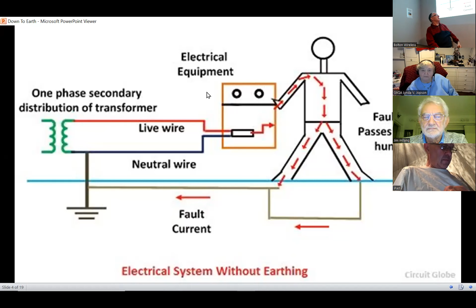Ooh, so earth is not all good? No - he's connected to earth and he's suffering because there is an earth. We get round that in electrical supply terms by making an earth connection to the chassis or cabinet of the unit, thereby providing a very low resistance, low impedance path to earth so that the voltage drop between earth and the cabinet is very low. So now he's only across a very low voltage.